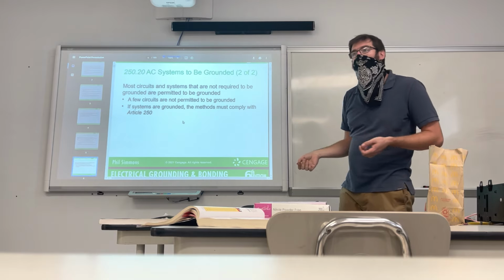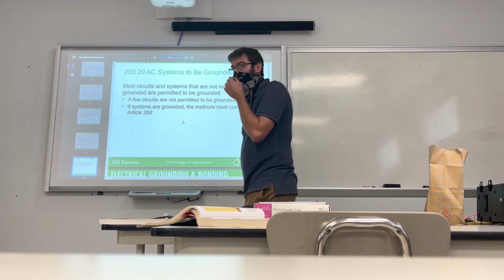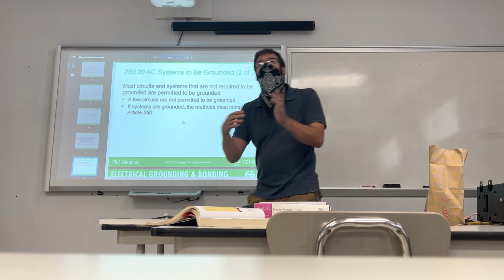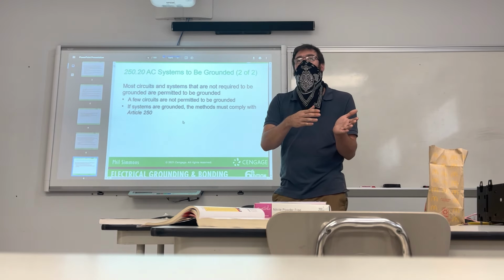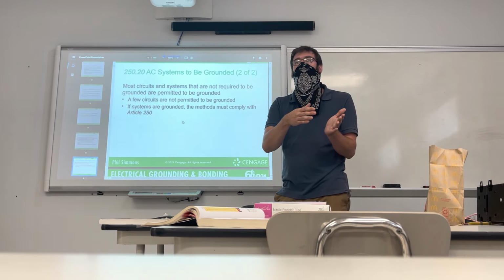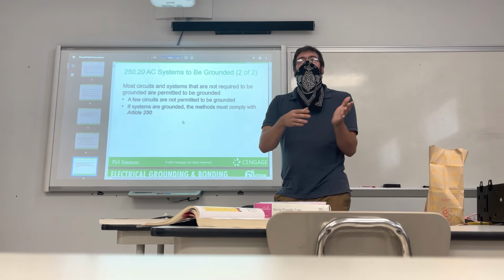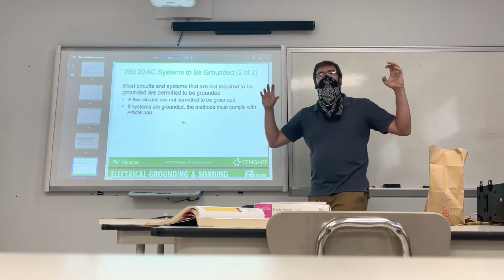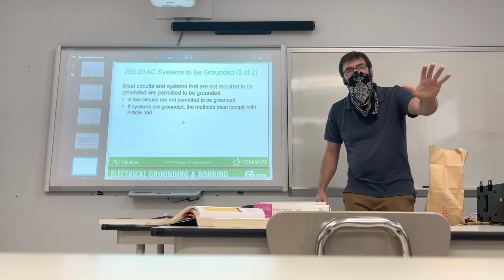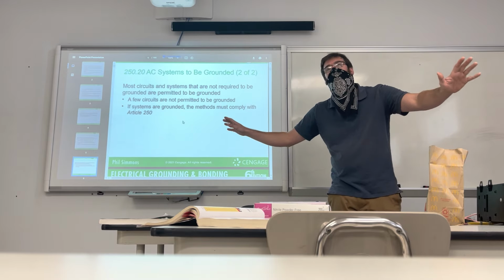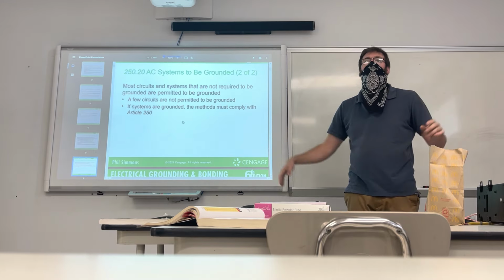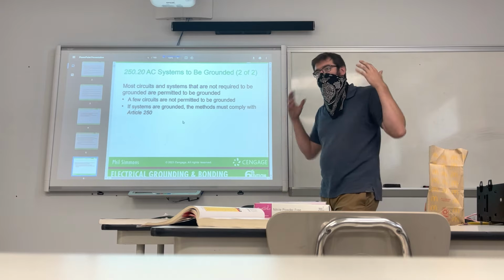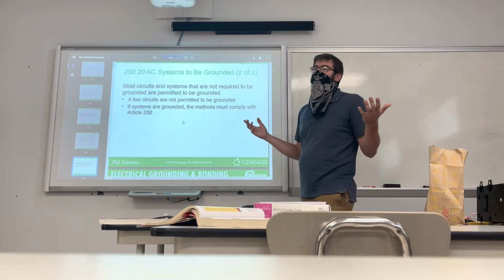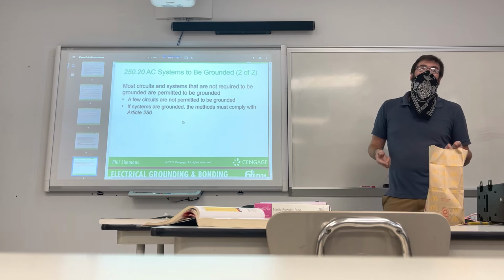Sure. Now, if that's an ungrounded system, there's no way for that to go back and provide an overload current situation for that breaker, so that breaker's never going to trip, all right? But now, the outside of that conduit is hot. So if you were to touch that conduit and touch something else that's grounded, what are you? Dead, right? But why do these systems do that? What's the purpose? So, like Phil said, it can continue to run.